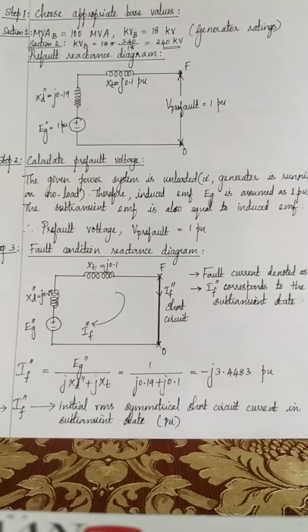Similarly, for the transformer also, with respect to the primary side, that is the 18 kilovolt side, if you calculate XT1 new, it will be j0.1 into 100 by 100 into 18 by 18 the whole square. So no change in the transformer reactance also. Okay, j0.1.